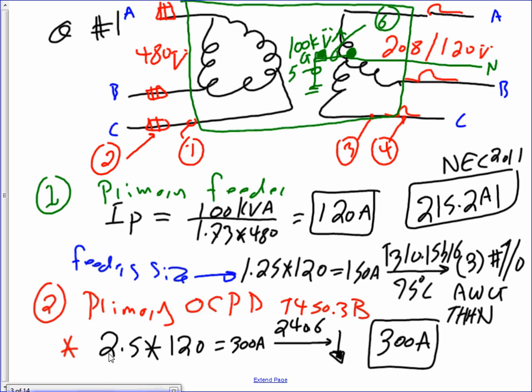Okay, any comments, any questions? Any comments, guys, any questions? So we sized the primary fuse and the primary conductor. These 2 things are done for you. So we go to the secondary side. Now we are done. All you have to do now is give this to an electrician with conduit and wire, and go wire. Give me a set of fuses with a disconnect. Bring your EMT conduit, put these conductors inside it, and off it goes. How many of you guys have the calculator? Calculator handy? So grab your calculator. We'll do the second one on the calculator.